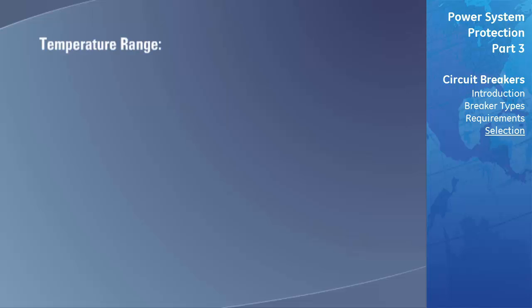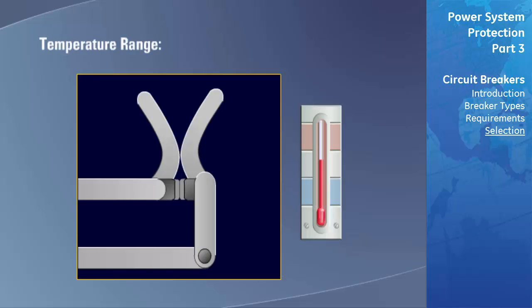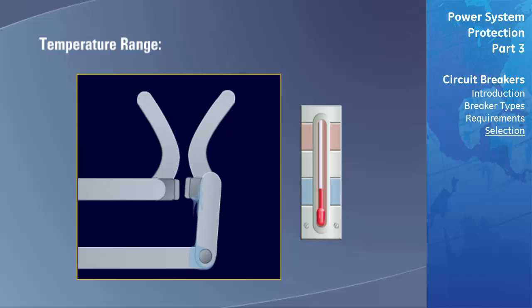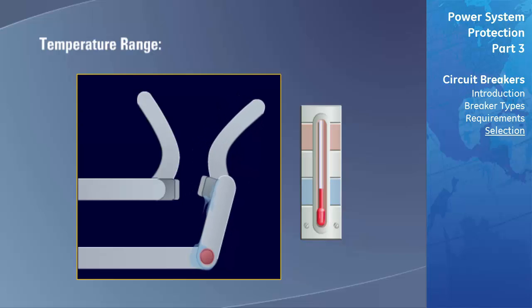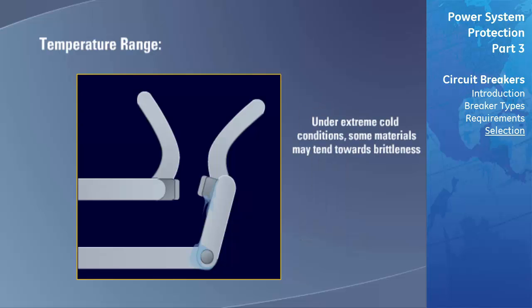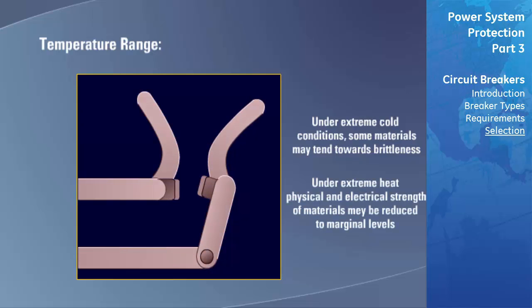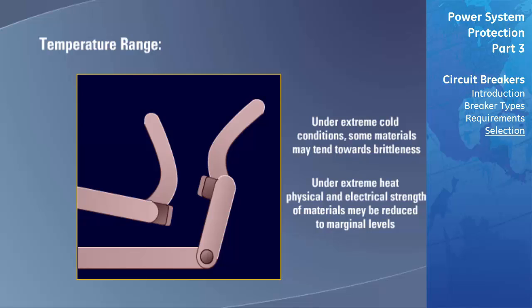Temperature affects circuit breaker operation. Below a specific temperature, mechanism operation may not be reliable due to possible freezing of condensation, freezing of lubricants, or mechanical interference from changes in physical dimensions of components. Some materials may tend toward brittleness in extreme cold. Under increased heat, physical or electrical strength limits of some materials may be reduced to marginal levels, some materials can begin to melt, and the useful life of insulation can be seriously reduced. The application engineer should take each of these factors into consideration.